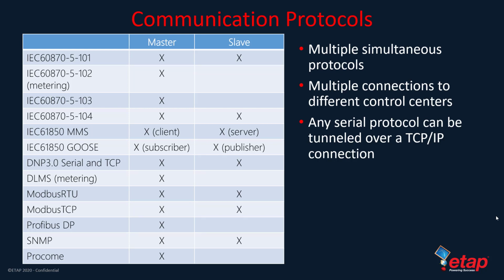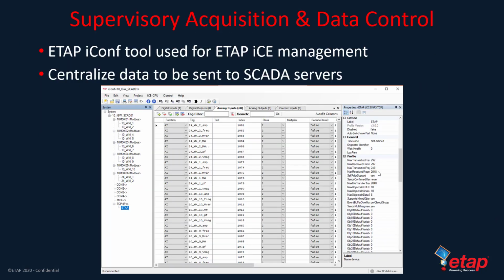The device also offers different types of communication protocols. So the data going to the device can be used with traditional protocols like Modbus, DNP3, IEC 61850, but it also includes an additional suite of protocols that this device can support either as a master or as a slave device. We have, in this case, the tool called ETAP iConf. That is the device configuration tool that you can use. Through this tool, you can take a look at your local devices that are directly connected to this device.